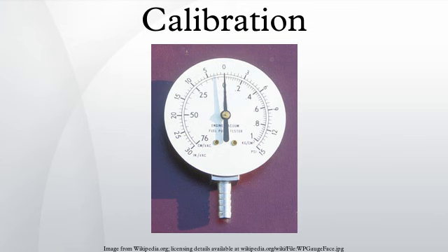This direct measurement of pressure as a height difference depends on the density of the manometer fluid, and a calibrated means of measuring the height difference. In a Bourdon tube, shown in the two views on the right, applied pressure entering from the bottom on the silver barbed pipe tries to straighten a curved tube, moving the free end of the tube that is mechanically connected to the pointer. This is indirect measurement that depends on calibration to read pressure or vacuum correctly. No self-calibration is possible, but generally the zero pressure state is correctable by the user.